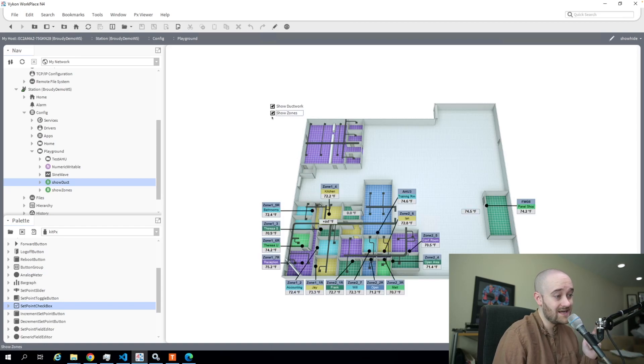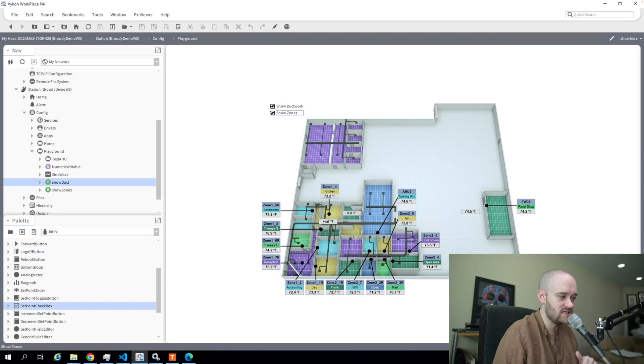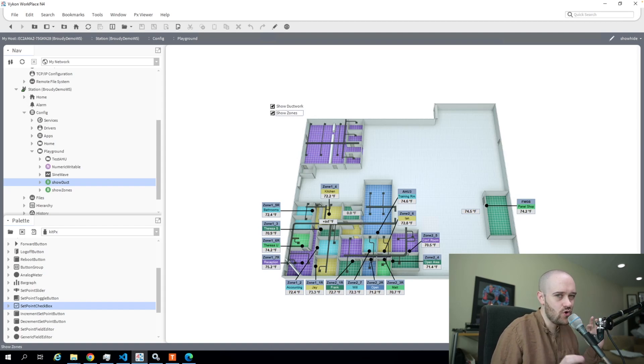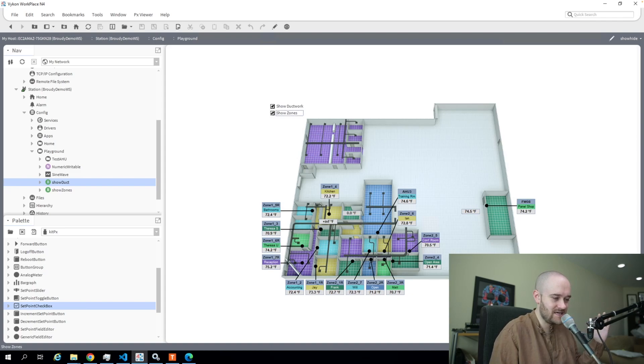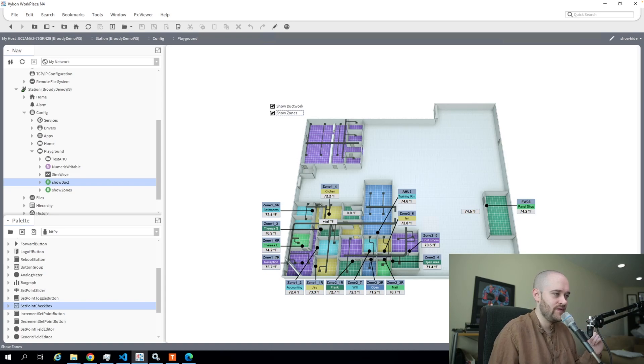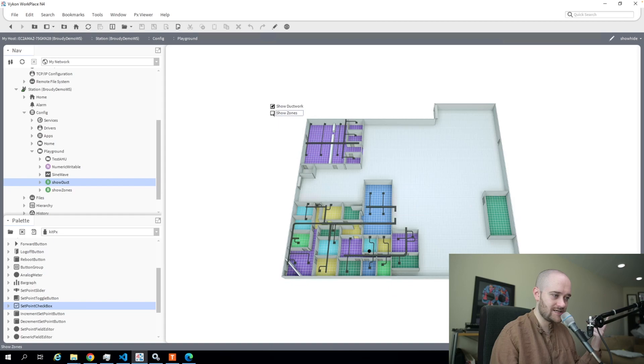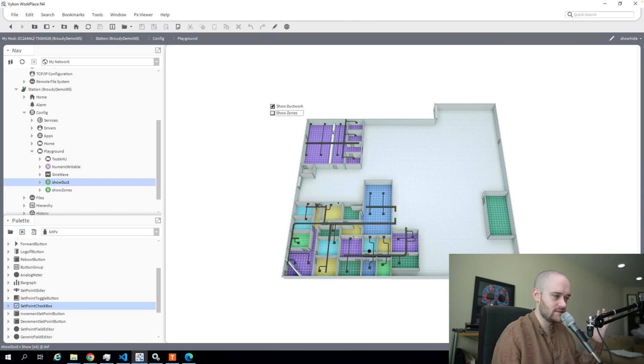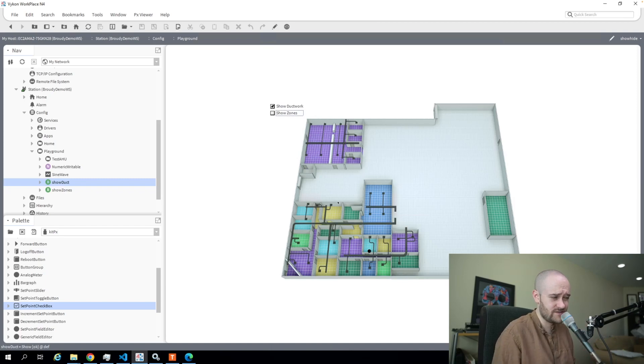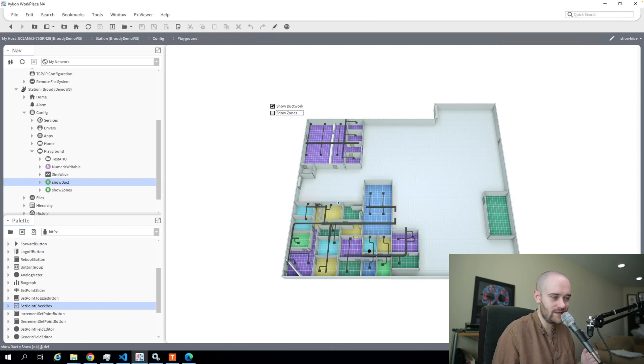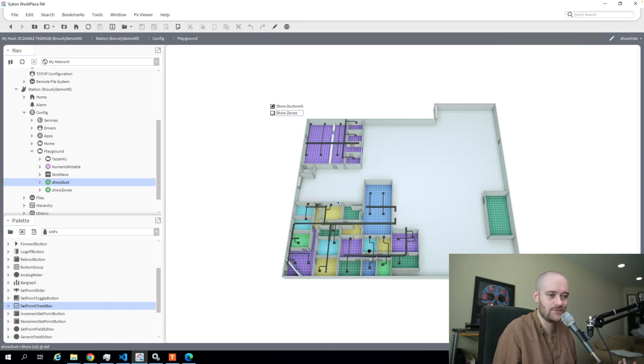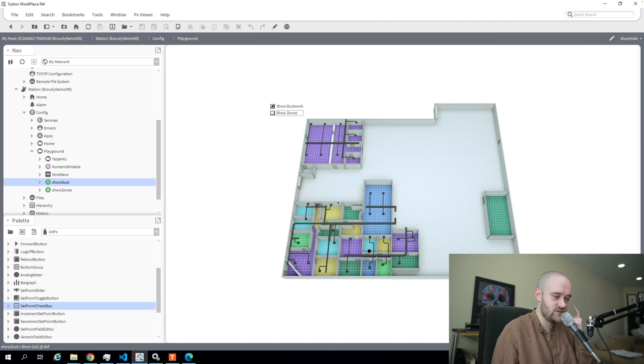So the one caveat that you need to know about all of this kind of pseudo interactivity is that these points behave the exact same way points do normally in Niagara, which means if one user that you have who's logged in to the system unchecks this box, that change will be made for every other user that's logged into the system. I think for the vast majority of systems this probably won't make a difference. You don't have a ton of people who are logged in at the same time who are going to be maybe running into this, plus it's only for a graphic, so the likelihood of it causing issues is pretty low. But it's just something to keep in mind.